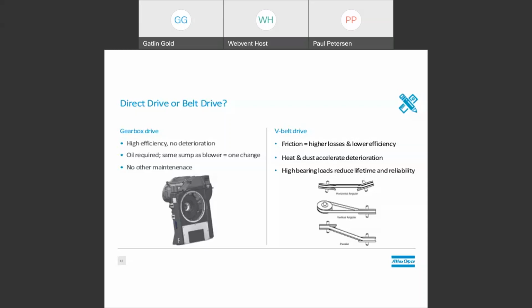So for that reason, Atlas Copco uses a shaft-mounted oil pump on our gearboxes, especially in our rotary screw blowers. Whenever the motor is spinning, all of the bearings and gears are force lubricated in the entire drivetrain, and that oil is filtered and cooled, resulting in the highest efficiency and the highest reliability. On some lower cost products like lobe blowers, we still offer belts and pulleys because they're a very cost effective solution.